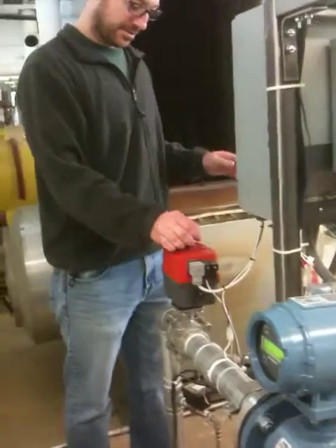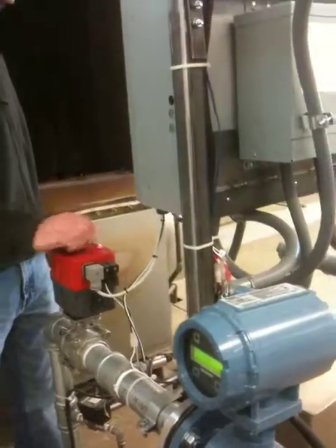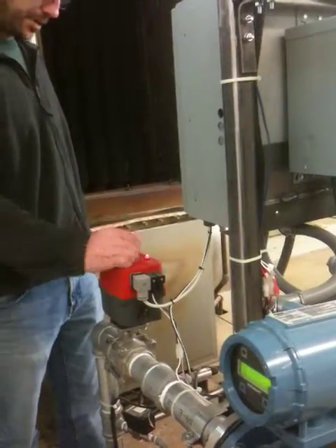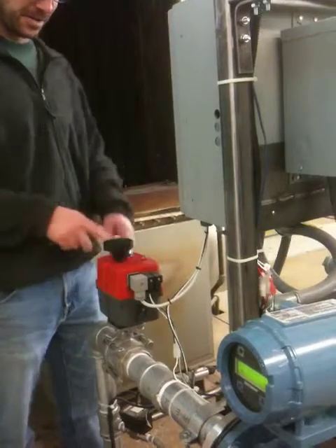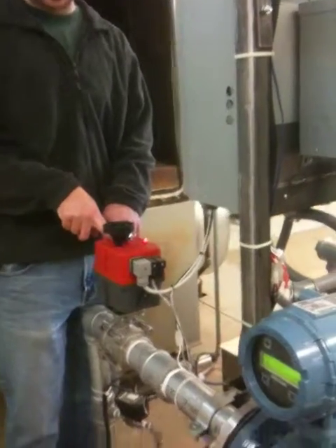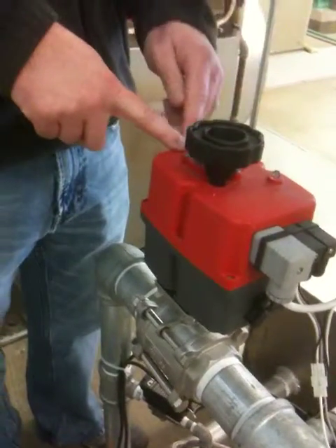This valve is a little bit tough to turn. It's not too bad though. Some parts of it get tough to turn, but when this indicator's at 90 degrees, it's fully open, and then just turn it around so that it gets to 0. Get at least like 10 points in between there. So just move it a little bit, and you'll see the flow change. A little bit, the flow change, and then little increments. Say 10 points, yeah, over to 0. Cool. Thank you. I'll be back in 2 minutes.